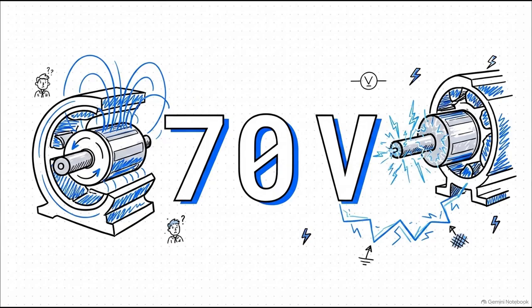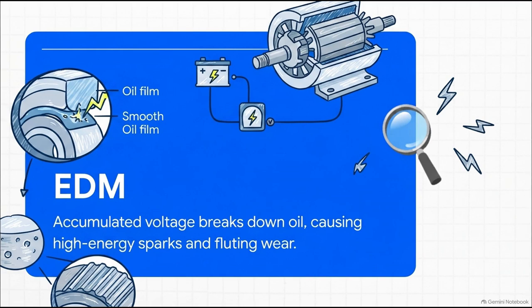Now, all that extreme energy has to go somewhere. It sneaks through parasitic capacitance between the stator and the rotor, building up what engineers call a common mode shaft voltage. We're talking 70 to 370 volts sitting right there on the spinning motor shaft itself. The shaft is basically electrically charged, just desperately looking for a way to ground itself. And this leads us to a highly destructive process known as electrical discharge machining, or EDM. So that accumulated 370 volts eventually punches straight through the thin protective oil film inside the motor's bearings. When it breaks through, bam, it acts like a microscopic lightning strike.